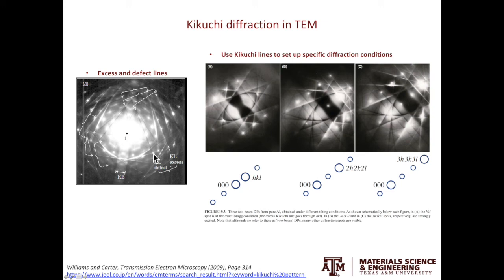After understanding what causes Kikuchi diffraction, let's look at how we can use Kikuchi lines. The first use is that Kikuchi lines can help us with tilting. In the example shown here, we have the direct beam and the diffracted beam — a classical two-beam condition with one G excited. In the middle tilting condition, one G is pretty dim but two G is bright, so this is a two-beam condition with two G excited. In the example on the right, one G is dim, two G is dim, three G is bright — a two-beam condition with three G excited. You will appreciate why this is important when we discuss weak beam dark field imaging.